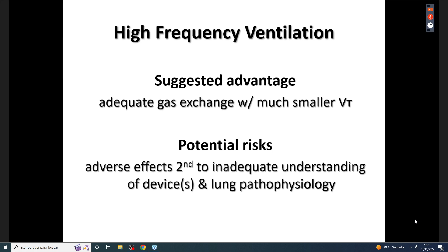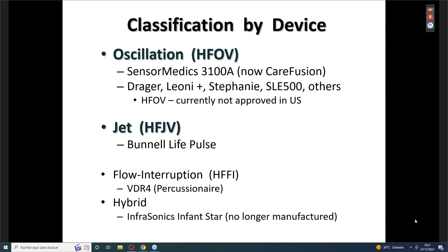The suggested advantage is that it provides adequate gas exchange with much smaller tidal volumes, but there are risks in using it. The main two devices that we have in the United States are the oscillatory device, the SensorMedics 3100, and the jet, the Bunnell Life Pulse. They're not currently FDA approved. Our colleagues in Asia, Europe, Canada, New Zealand, and Australia do have access to other high-frequency oscillator devices that also allow a volume-targeted approach to high frequency.